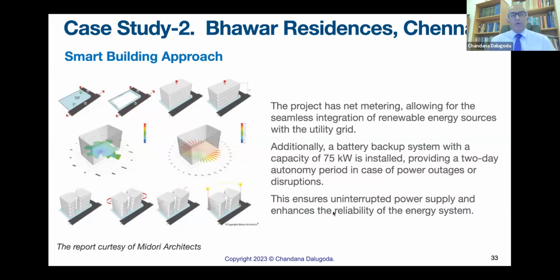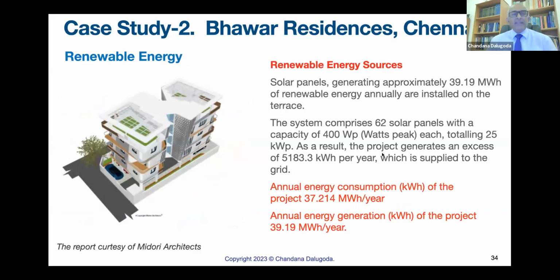So we can now summarize and then learn how the net zero has come. Renewable sources: solar panels have been installed. They are generating approximately 39.19 megawatt hours of renewable energy annually. They are on the terrace. The system comprises 62 solar panels with a capacity of 400 watt peak each, totaling 25 kilowatt peak. As a result, the project generates an excess of 5183.3 kilowatt hours per year.